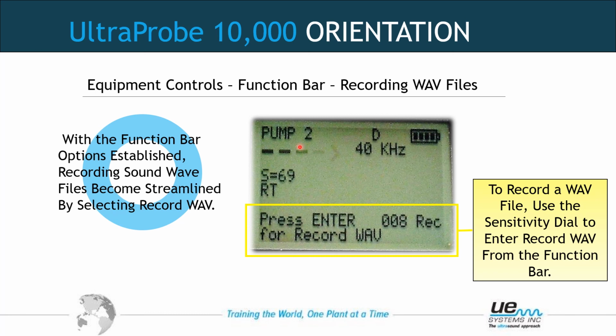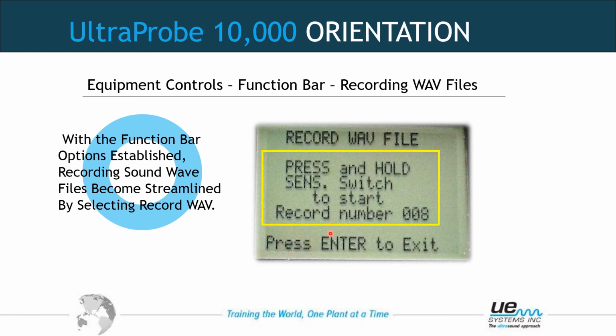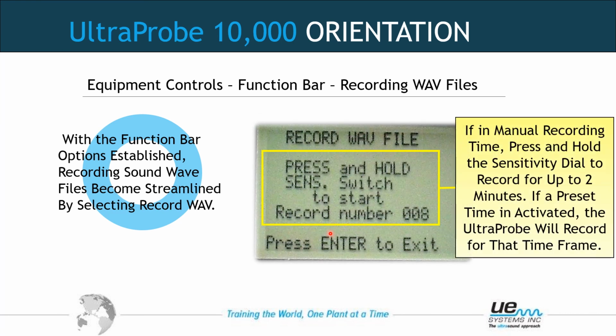So once we get everything set up, a decibel, 2 to 4 bars on the intensity meter that's not showing here, then we press the yellow button to record. And the first screen we come to is press and hold the sensitivity switch to start record number 8. By the way this is written, I know that this is in a manual mode for the recording. I need to press and hold the sensitivity switch in and count off in my head for how long I want to record. If it said press sensitivity switch to start, that would tell me that it is in an automatic preset time of 5, 10, 15, 20, 25, or 30 seconds. So I press it and hold it.